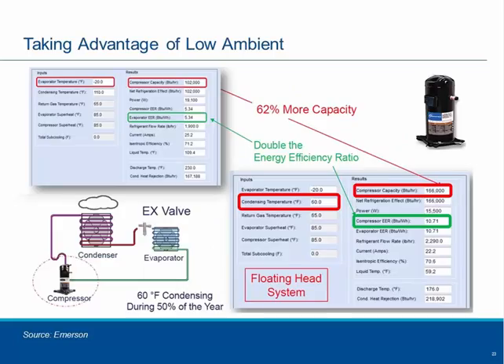This is a couple of screenshots of a calculator tool that's available for free download from EmersonClimate.com. But it shows for a freezer, minus 20 degree evaporator freezer, the difference in capacity and efficiency if you run 110 degree Fahrenheit condensing temperature or if you drop it down to 60 degrees. And I pick 60 degrees because in many of these locations, over half of the hours in the year do fall below 60 degrees condensing.